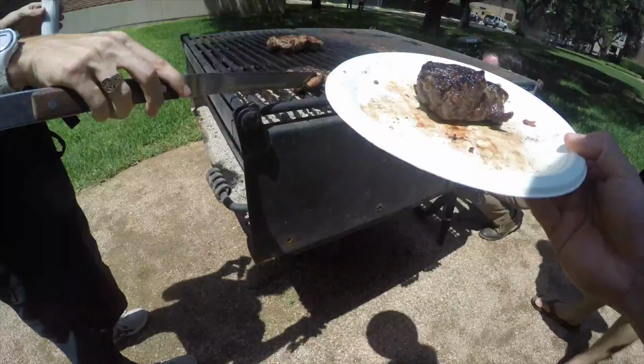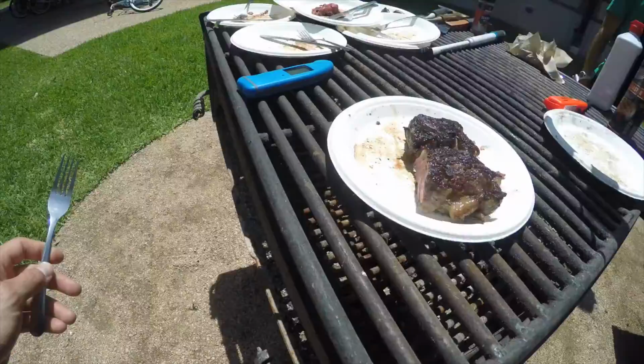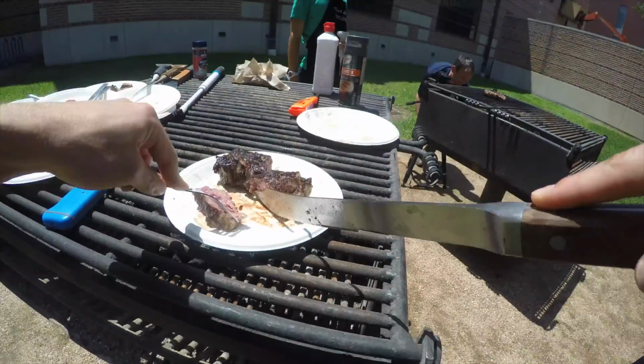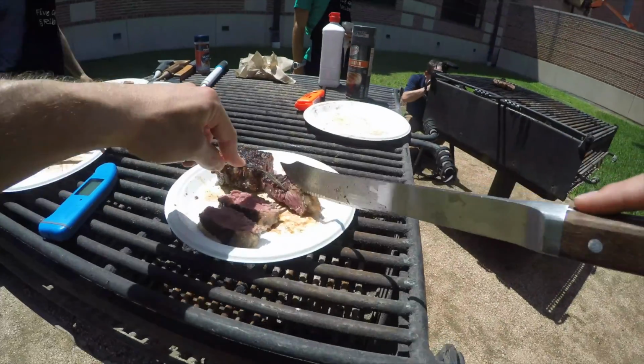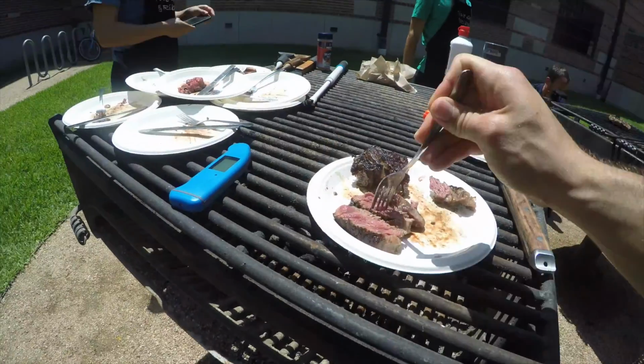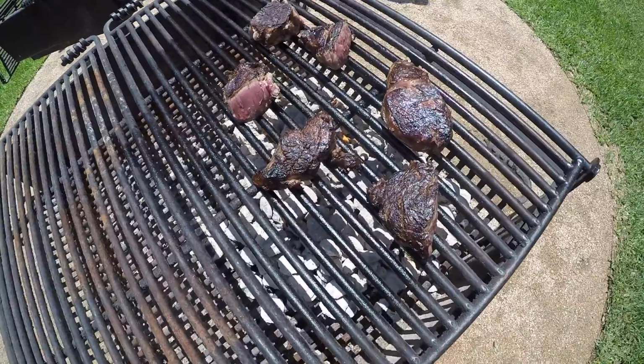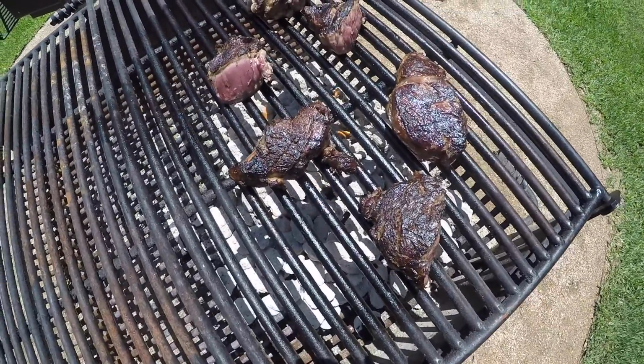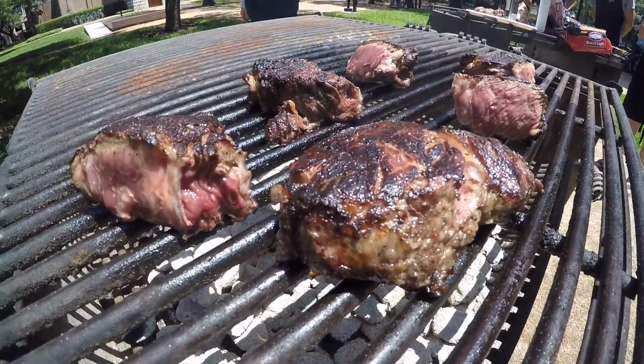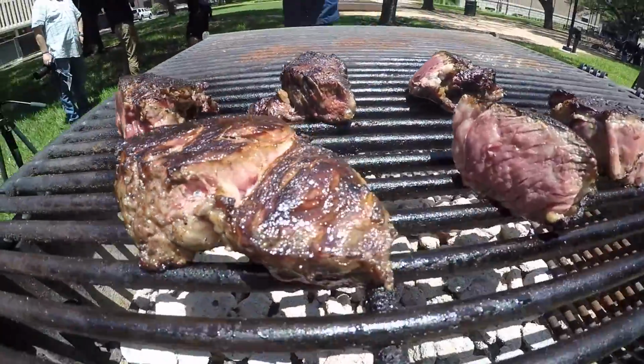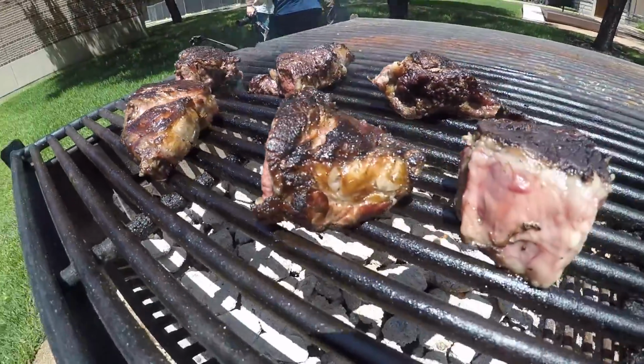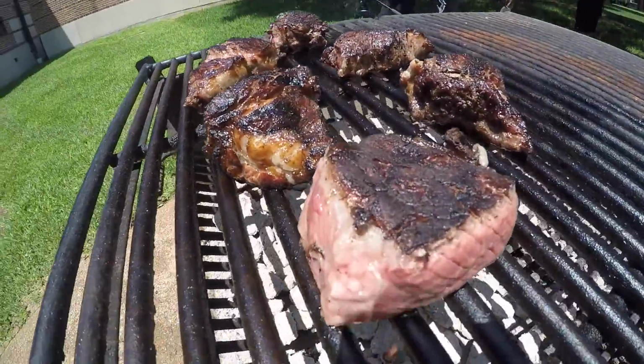The way we overcame that obstacle was by placing the individual thermistors in sensor caps and adhering them with thermal paste, which is highly heat conductive relative to the probe material, an ABS printed plastic. We've also got another version with PEEK plastic, which is more resistant to the higher temperatures of the flame.